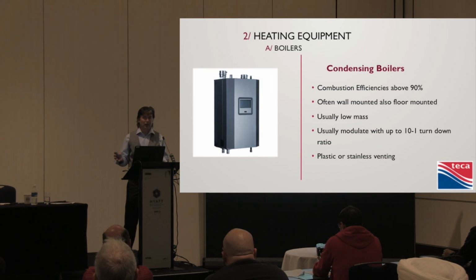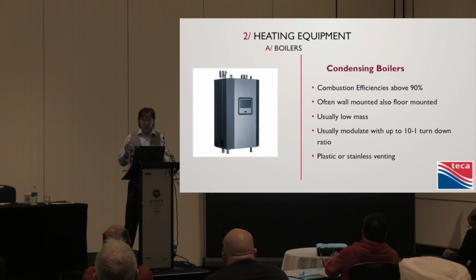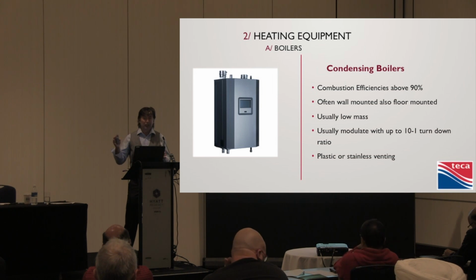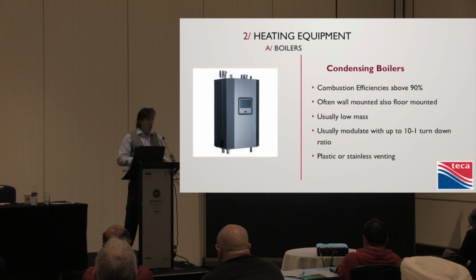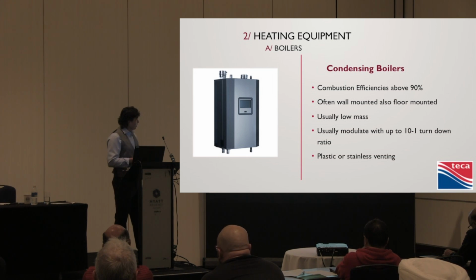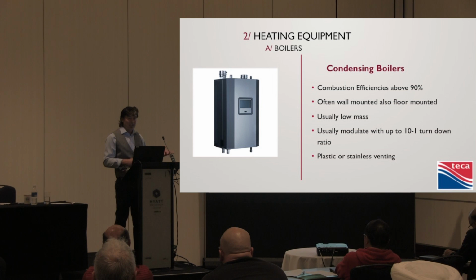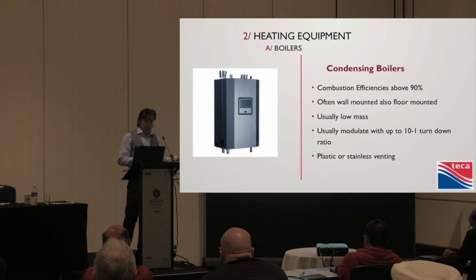But how often are we actually there? Like 2% of the time, we're actually at a design temperature. The rest of the time, we're somewhere below that, and usually below half of that. Correct me if I'm wrong at any time, David. So that's the nature of this guy here, 10-to-1. So it's a 100,000 BTU boiler, but it's also a 10,000 BTU boiler. That's the beauty of it.